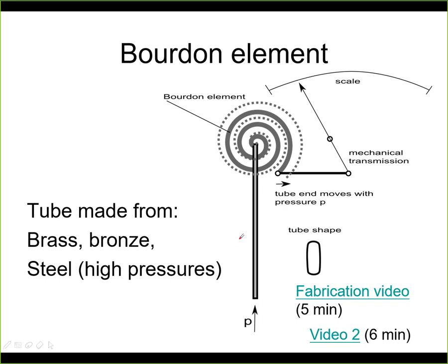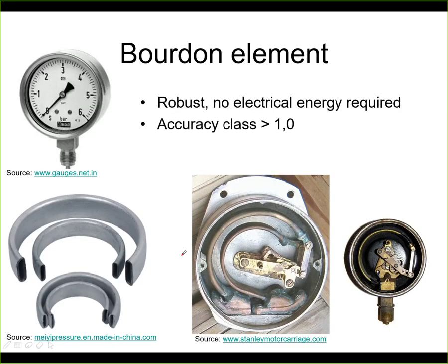Now there is a very good video about how this is produced, so I recommend you take a look at this link, where you can actually see the production of such Bourdon tubes and also the functions of the lever system and of the whole instrument. Now the tube is made from different materials, and the material is selected based on the pressure range. For relatively lower pressures, the Bourdon element is made from brass or bronze, and for high pressures it is made from steel. Now let's take a look at how this looks.